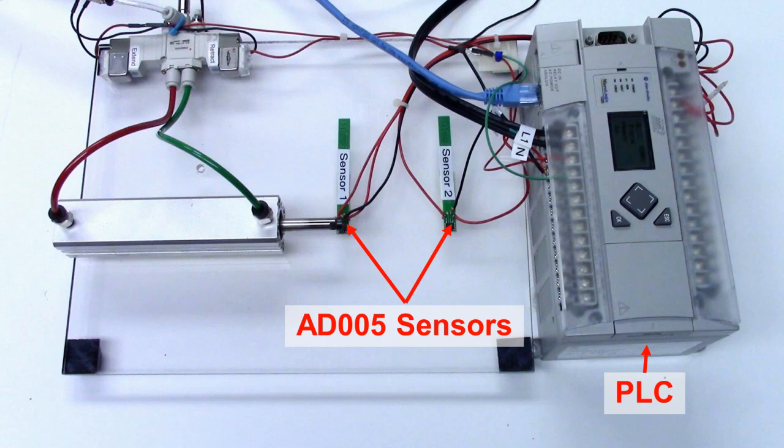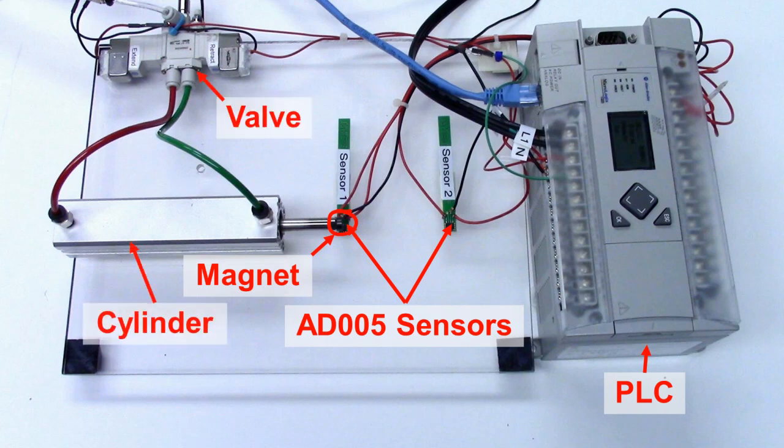The two sensors set the two travel limits. There's a disc magnet on the piston. We have a pneumatic cylinder, a 3 position 5 port directional control valve with exhaust center. With a 3 position valve we can extend, reverse, or stop the cylinder.